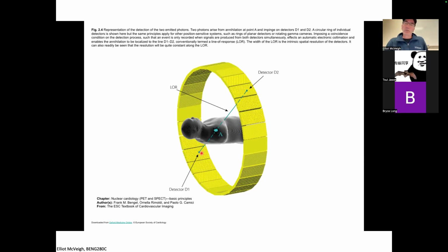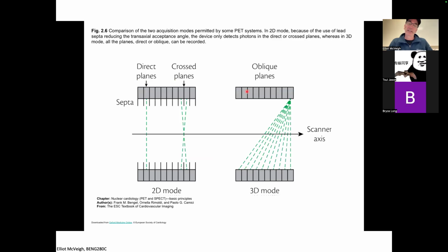And then another thing we have to take into consideration is that this will produce a flash of light. That large energy photon, the half MeV photon, causes a flash of light in a crystal, just the way it did in SPECT, basically. And then we're going to figure out where that flash happened using the same techniques we did in SPECT. So the crystal has to be a little bit thick, a few centimeters thick, because it's a high energy photon and they tend to go through stuff, right? And so that gives you a loss of resolution because the crystals are thick.